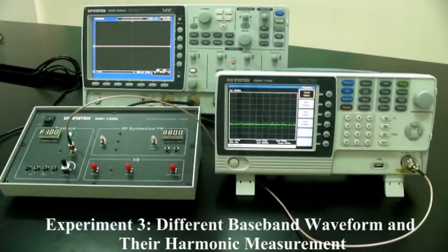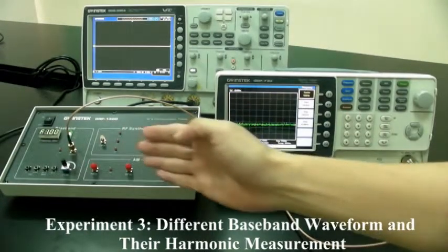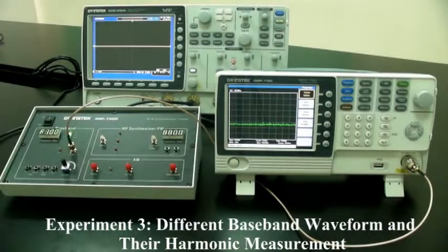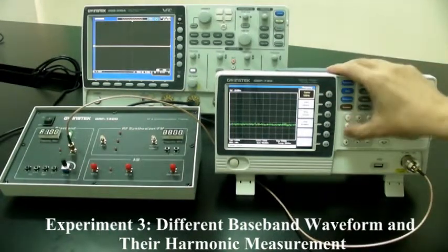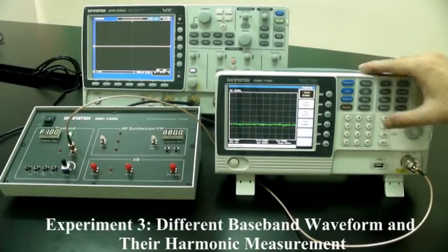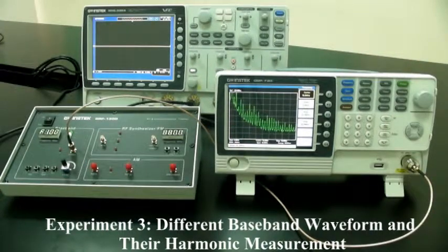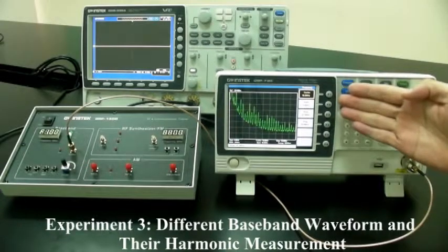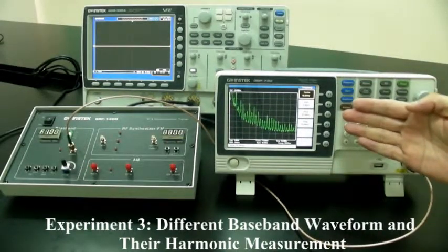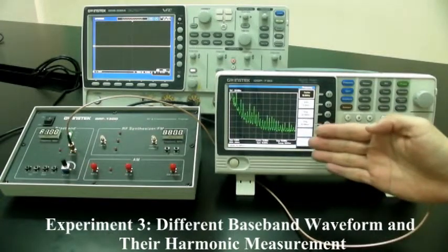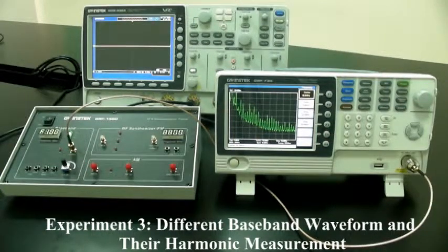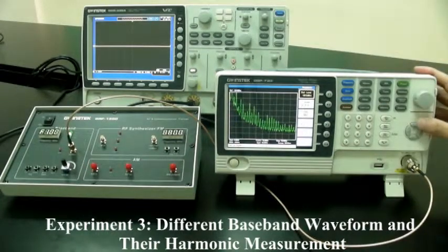Connect the baseband signal from the output port on the GRF-1300 to the input terminal on GSP-730 with the RF cable. Set the GSP-730 as follows: Center frequency: 15 MHz. Start frequency: 0 kHz. Stop frequency: 30 MHz. Span: 30 MHz. Reference level: 0 dBm.